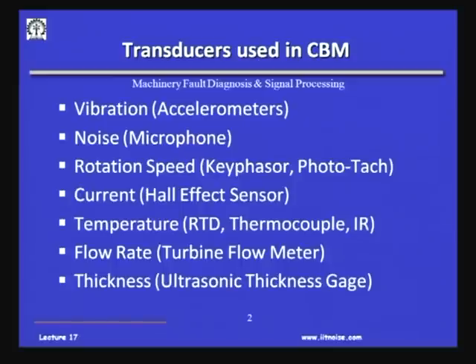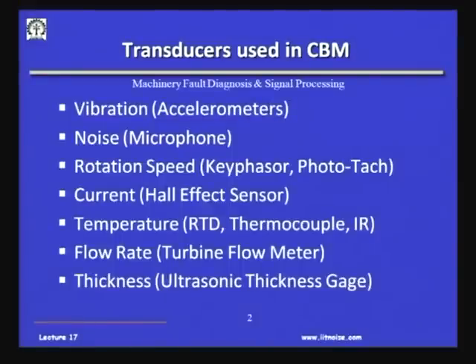Sometimes people even do portable X-ray radiography of the tube from the outside, particularly in boiler tubes. When there is lot of scale formation because of water flowing through the pipelines, the effective diameter for flow reduces, and this can be measured by techniques like radiography or ultrasonic thickness gauge. If there are internal cracks in the structure which cannot be seen visibly, an ultrasonic probe can be used to detect the presence of the crack.